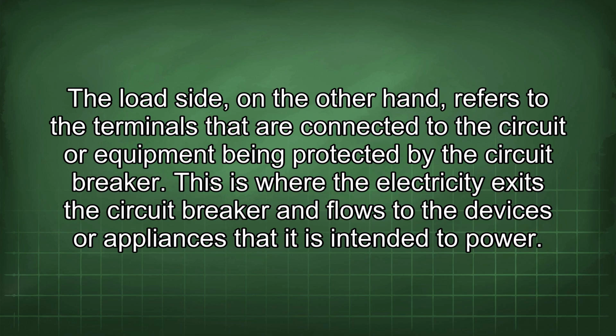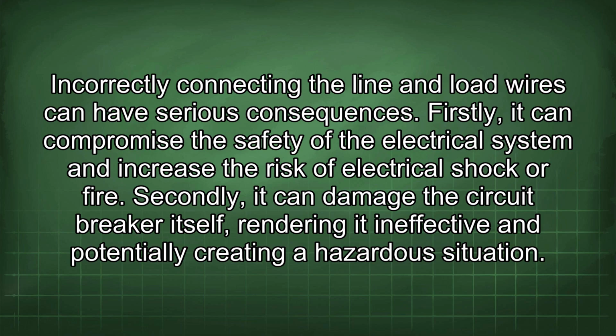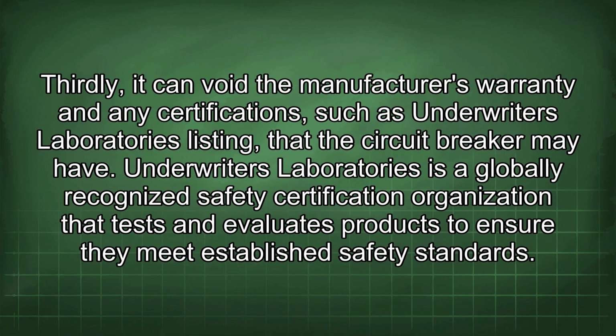to power. Incorrectly connecting the line and load wires can have serious consequences. Firstly, it can compromise the safety of the electrical system and increase the risk of electrical shock or fire. Secondly, it can damage the circuit breaker itself, rendering it ineffective and potentially creating a hazardous situation. Thirdly, it can void the manufacturer's warranty and any certifications, such as Underwriters Laboratories listing, that the circuit breaker may have.